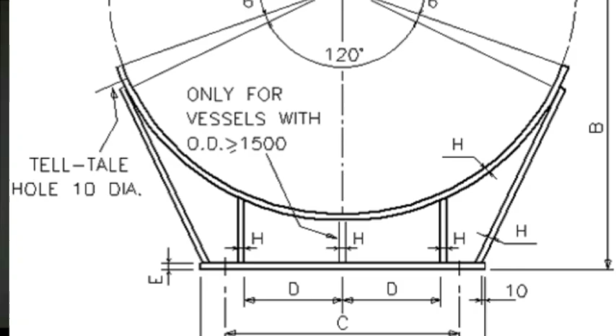I have to transfer wind and seismic loads. If I design the top heat exchanger, I have center of gravity and weight for all operating conditions, empty condition and hydro condition. I just have to enter the weight and center of gravity of the top heat exchanger, not on top of the saddle. The correct way is you should design it and add all weights at the proper location.